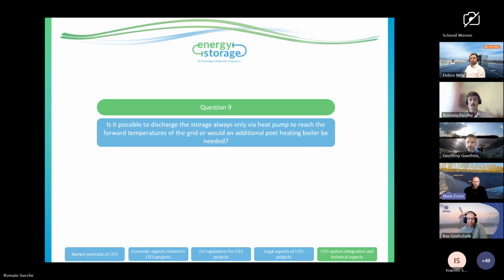If you're using the heat pump just for this and not using anything else, then the heat pump capacity should be designed to meet the highest heat demand and the worst conditions. So that's the lowest temperature on the cold side and the highest temperature on the warm side. And the other solution will be that the system is not able to provide all the required heat, so you need boilers anyway. And if you have boilers in the system, you can use them in series with the heat pump, and then use the boilers for post heating. And the heat pump can be operated at a lower exit temperature from the warm side, and therefore also have increased COP.